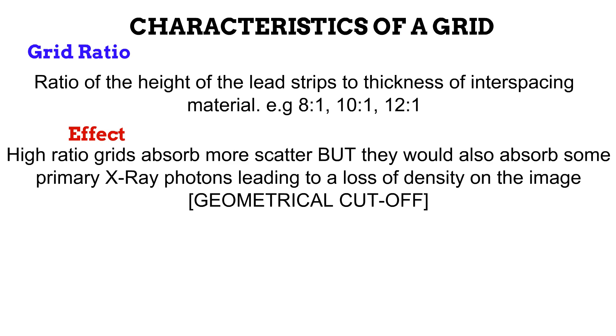However, because the lead strips are thicker, high ratio grids are also likely to absorb some primary photons. This leads to a reduction in density on the radiographic image, because some photons that should form useful densities are absorbed and do not reach the image receptor. This is known as geometrical cutoff, and it is for this reason that when a radiographer uses a grid, he or she needs to increase the exposure factors compared to when a grid is not used, to compensate for the useful photons absorbed.